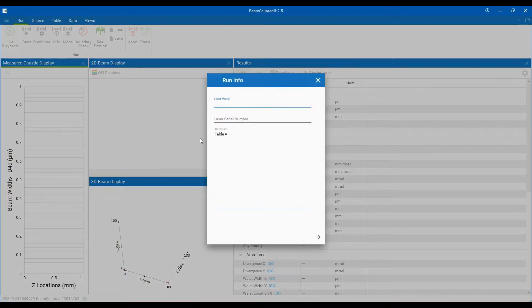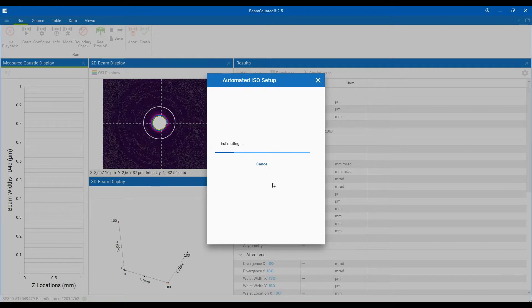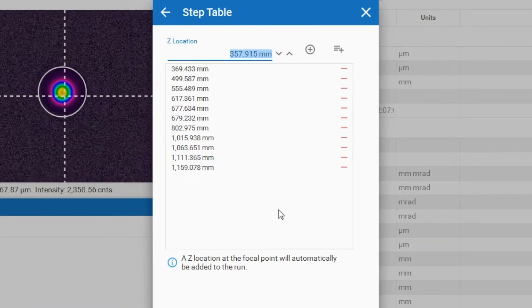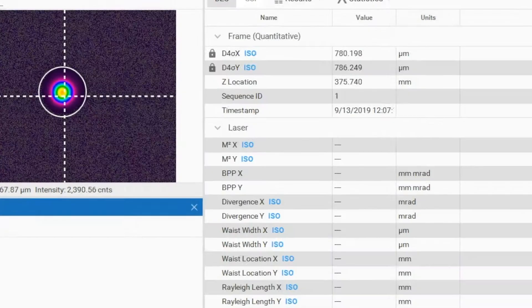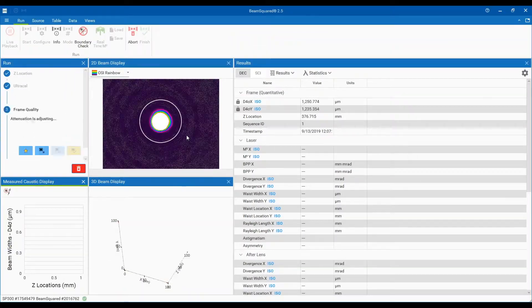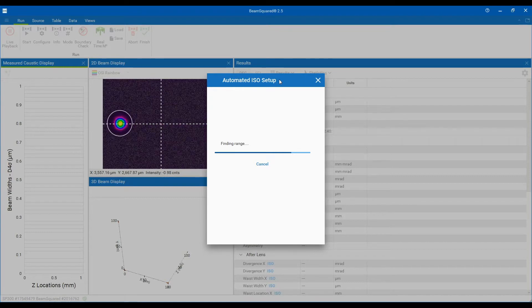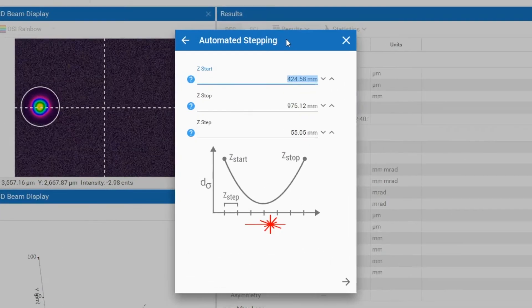The new automated ISO setup feature is selected in the measure method window that is part of the Beam Squared configure feature. If successful, the automated ISO setup will populate the step table in the Beam Squared software so an ISO compliant beam propagation measurement can be made. If the automated ISO setup is unable to construct an ISO compliant beam propagation measurement, the application will go into automated stepping mode.